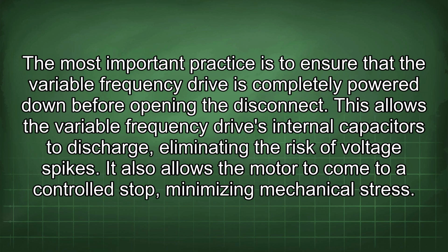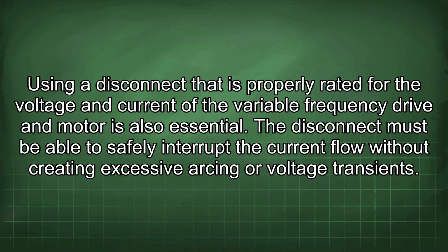The most important practice is to ensure that the variable frequency drive is completely powered down before opening the disconnect. This allows the variable frequency drive's internal capacitors to discharge, eliminating the risk of voltage spikes. It also allows the motor to come to a controlled stop, minimizing mechanical stress. Using a disconnect that is properly rated for the voltage and current of the variable frequency drive and motor is also essential. The disconnect must be able to safely interrupt the current flow without creating excessive arcing or voltage transients.